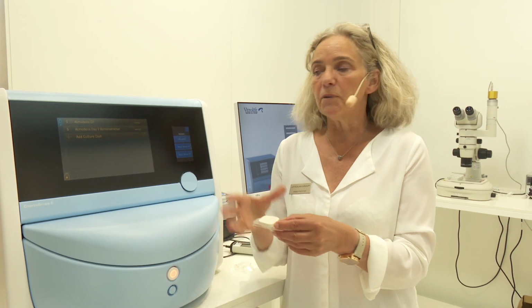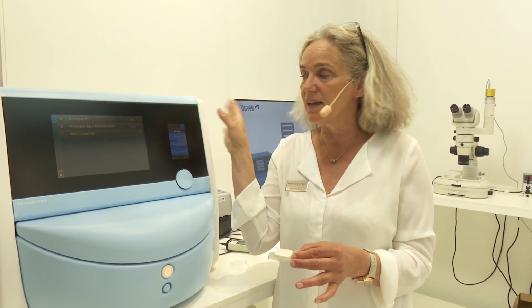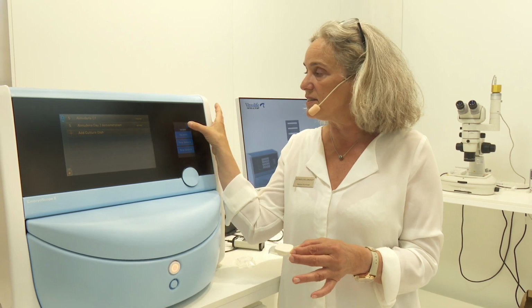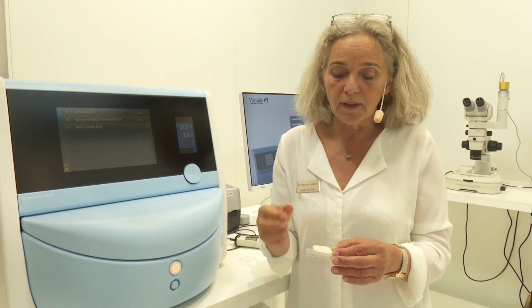And before you take it out again for your measurement the next day, of course, you had validated everything before, so you make sure that the sensors are as they should be. And then you calibrate also your pH meter. This is very, very important. So everything is ready for your measurement, because when you have taken it out, it is exposed to the environment outside, so your measurement should be done immediately.